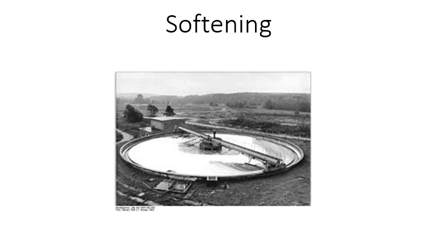For every 1 ton of lime used, 2 to 3 tons of waste sludge can be produced. Lime softening's high pH tends to set the color. Color should be removed by coagulation, at a pH of 6 to 7. Operators should know what the source water hardness is and what the finished water hardness goal is. The chemical dosage is based on the desired finished water hardness goal. There was math, but these are audio notes, so I'm not doing math.